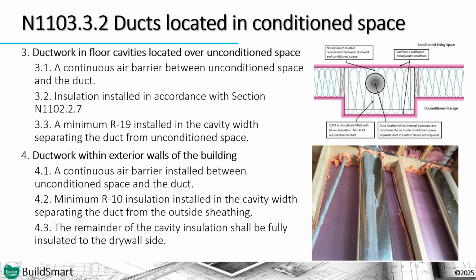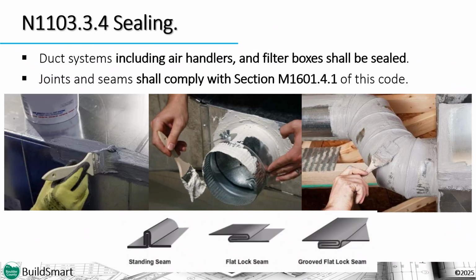Ductwork located in floors over garages or in cantilevers, or ductwork installed in insulated walls that are used to get duct from the basement to the second floor, for example. Regardless of this allowance in the code and the benefits to the HERS Energy Rating Index score modeling, it is still not the most recommended way to install ductwork. Best practices for performance would be to clearly bring it into the conditioned space of the house.